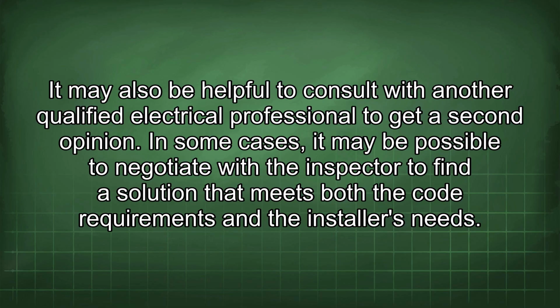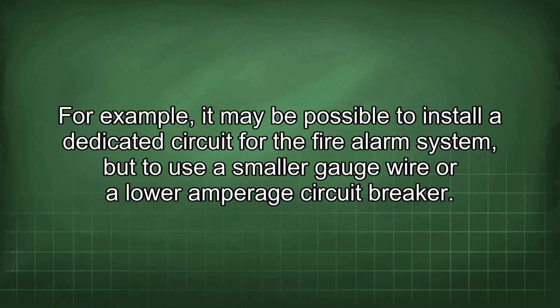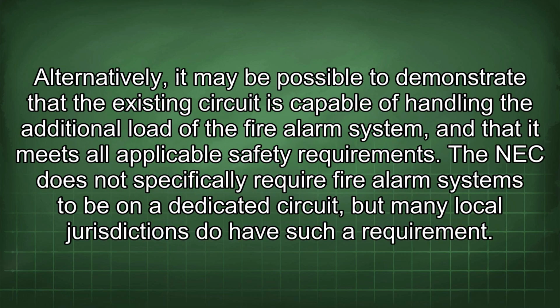In some cases, it may be possible to negotiate with the inspector to find a solution that meets both the code requirements and the installer's needs. For example, it may be possible to install a dedicated circuit for the fire alarm system, but to use a smaller gauge wire or a lower amperage circuit breaker. Alternatively, it may be possible to demonstrate that the existing circuit is capable of handling the additional load of the fire alarm system and that it meets all applicable safety requirements.